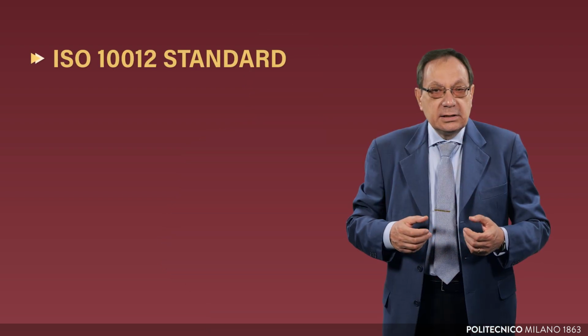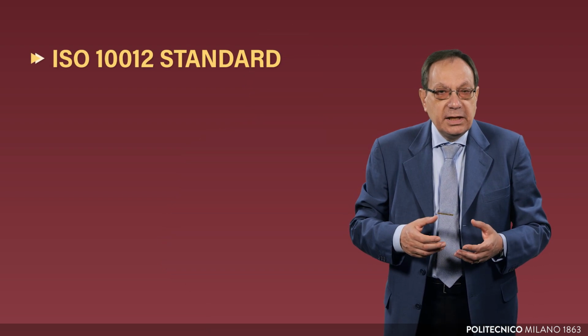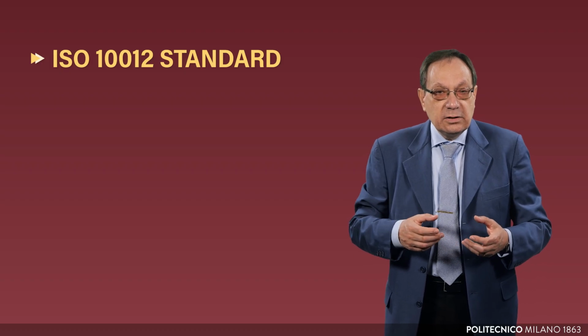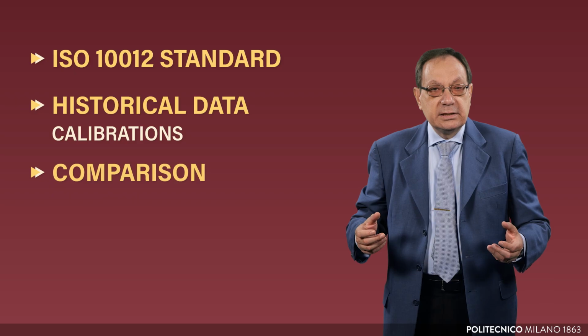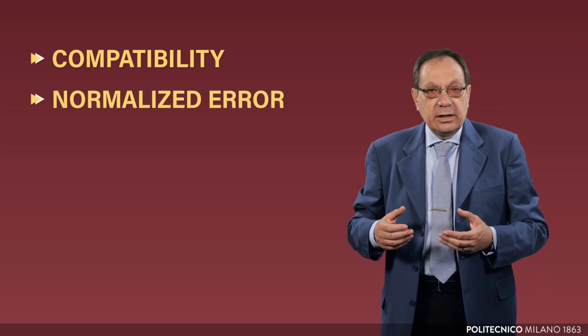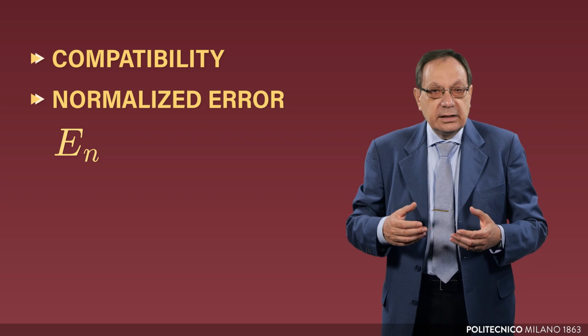However, there are several cases in which it is not possible to carry out comparisons between a statistically significant number of similar instruments. Even in these cases, it is necessary to establish when a new calibration should be carried out to prevent the instrument from no longer meeting the required standards. The ISO 10012 standard suggests several methods essentially based on the analysis of historical calibration data and their comparison. For example, one can assess the compatibility between the results of successive calibrations by evaluating the normalized error E_N and analyzing its trend over time.